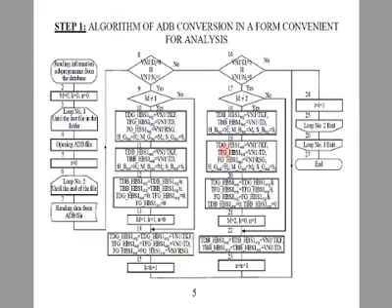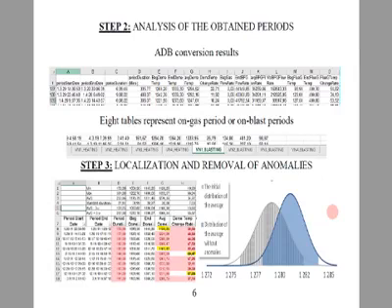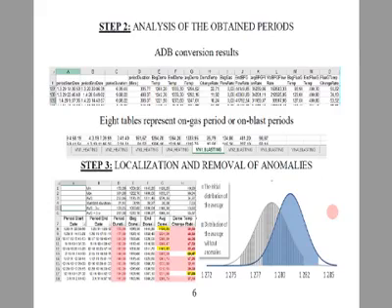The operation of each HBS will be described by characteristics including the time of the beginning and end of the periods, the duration of the periods, the beginning and end values of the dome temperature, the flue gases temperature, and the temperature of blast air. Also included are the average integral value of the dome temperature, flue gases temperature, blast temperature, and inlet to HBS. The volume of consumed BFG is the average integral flow rate of the BFG during the period.